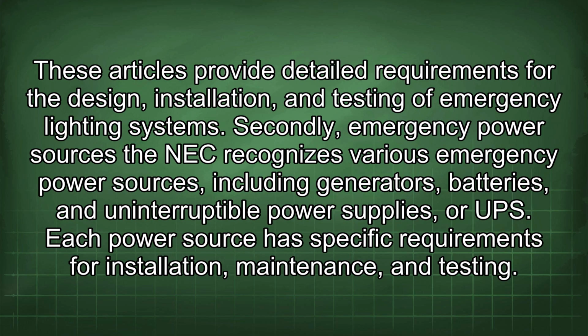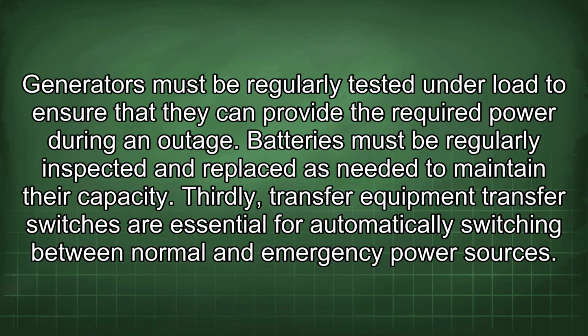Secondly, emergency power sources. The NEC recognizes various emergency power sources, including generators, batteries, and uninterruptible power supplies, or UPS. Each power source has specific requirements for installation, maintenance, and testing. Generators must be regularly tested under load to ensure that they can provide the required power during an outage. Batteries must be regularly inspected and replaced as needed to maintain their capacity.